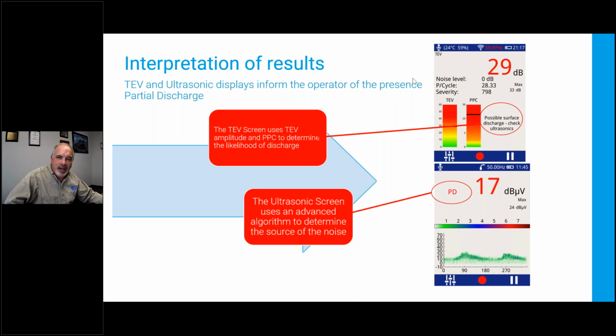We believe that it helps as opposed to just giving the customer a very simple screen. They want the data, they want numbers, they want something they can see, but they also want a little help because ultrasonic testing or TEV testing isn't something you're going to do every day. So if it comes up and says it's possible surface discharge, use the ultrasonic, or on the ultrasonic screen it may say PD or noise. These are built-in algorithms that help the user interpret the data, but we're still going to give you all the data because we're technical people. We like data, but we also like someone to tell us what it means.